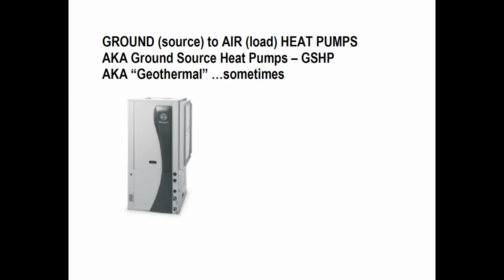The current most common one that I get involved with is ground loop, where we drill a hole in the ground, we put a tube with a U at the bottom down into the ground and pump fluid through that. We connect the outside of those tubes to the ground with what we call a grout. It's a conductive, semi-solid material that allows the energy to flow from the fluid inside the tubes out or in, depending on air conditioning or heating mode.